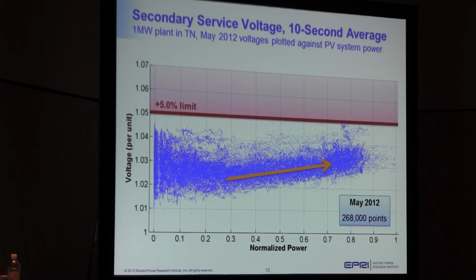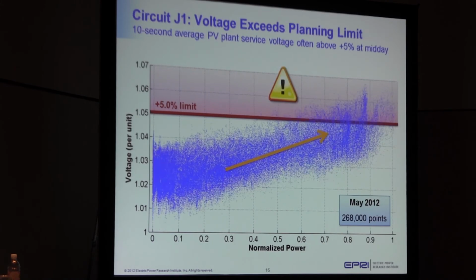This is for the entire month of May, so we have about 270,000 data points shown here. The 5% limit is a threshold that you don't want to exceed for planning purposes. Robert mentioned it earlier. Now let's jump over to circuit J1. We saw the circuit characteristics on the previous slide. This has a 1.7 megawatt PV in a couple of different places on the circuit, and you can see in the same month of May, we do exceed that planning limit.